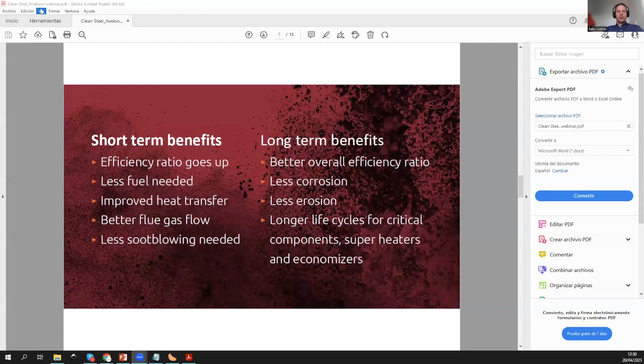So what are the benefits? Depending on the client, some of our clients want as quick a cleaning as possible, because sometimes the annual maintenance breaks are only a couple of days or so. Some of our clients prefer to get a kind of new boiler. So they get the efficiency ratio up, they can use less soot blowing, they get a better flue gas flow, improved heat transfer, less fuel in some cases to produce the same amount of energy.